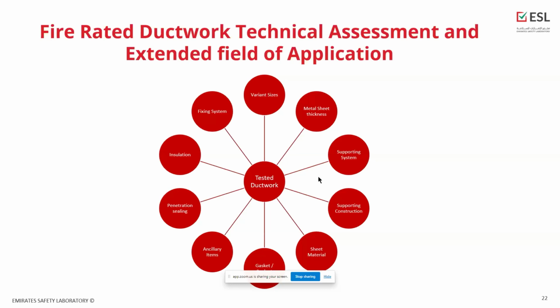So to prove to the end user or your client that this ductwork system is capable of performing under different conditions, you need a certification proving that by assessment for duct type, for ducts tested to BS 476 Part 24, and also using the extended field of application for ventilation ducts to EN standard by using 15882 Part 1. This step will help you to extend. We can see here, you can extend the various sizes and material sheets.